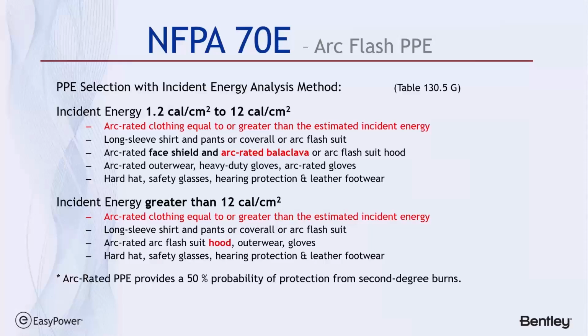Okay, once we've determined our incident energy and working distance, NFPA 70E directs us to this set of discussions. One is for an incident energy between 1.2 calories and 12 calories, and the other is for incident energy greater than 12 calories. The caveat is that as long as our PPE is rated equal to or greater than the estimated incident energy, then this description applies.